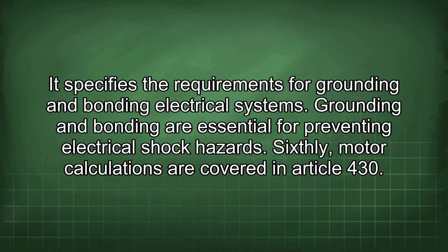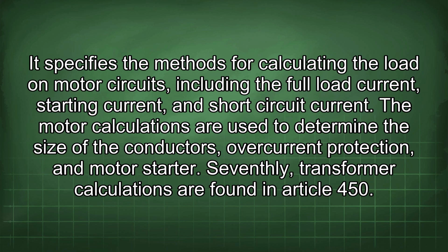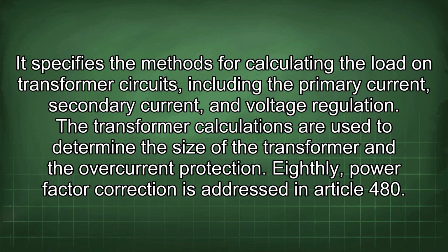Sixthly, motor calculations are covered in Article 430. It specifies the methods for calculating the load on motor circuits, including the full load current, starting current, and short circuit current. The motor calculations are used to determine the size of the conductors, overcurrent protection, and motor starter. Seventhly, transformer calculations are found in Article 450. It specifies the methods for calculating the load on transformer circuits, including the primary current, secondary current, and voltage regulation. The transformer calculations are used to determine the size of the transformer and the overcurrent protection.